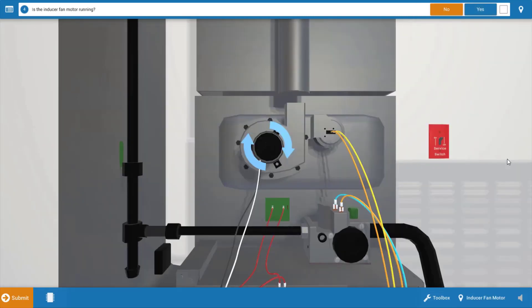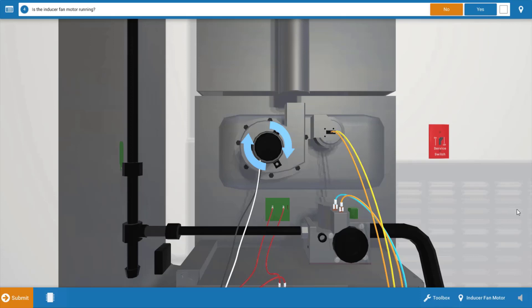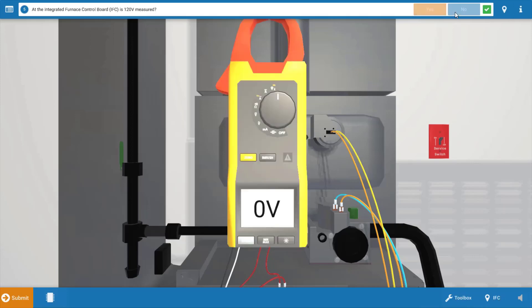Our next step is to take a brief inventory of the sequence of operations and the loads that actually start. When you turn the thermostat to call for heat, the first load that should operate would be the inducer or combustion air blower shown right here. As evidenced by the stationary arrows, this is not running, so we're going to click no on the procedure guide.